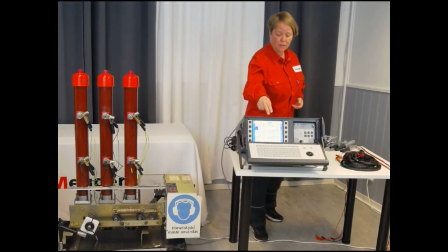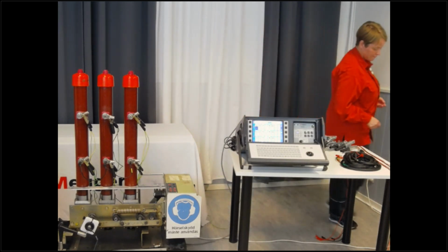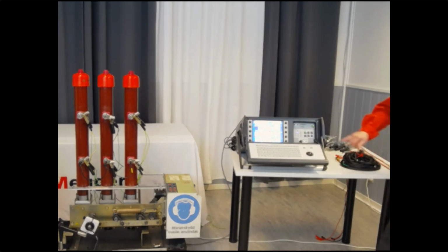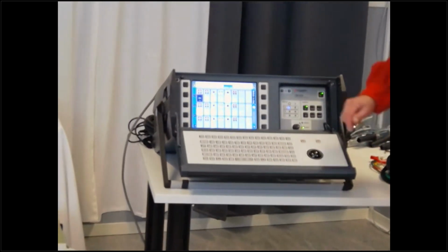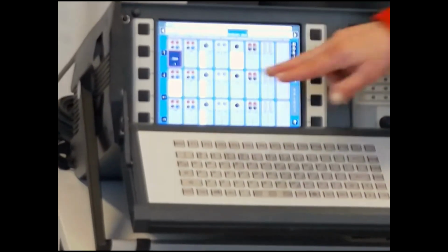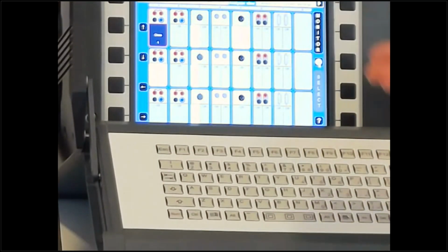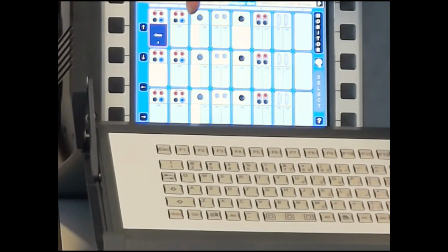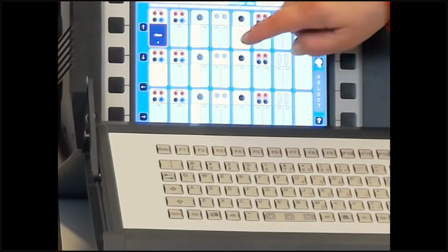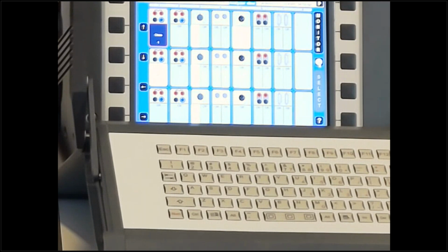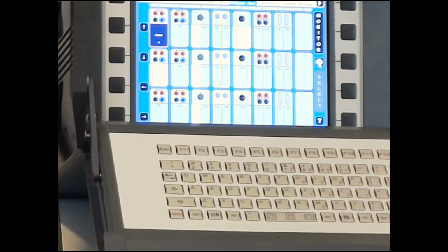If you see in the window here, it shows the configuration of this specific instrument, and this has control and control, double controls. Why? We have controls for close and for open, because we want to be able to control them separately if we want to do that. We have a normal timing module, and we have this dual ground timing module. So these two modules work together during this measurement.